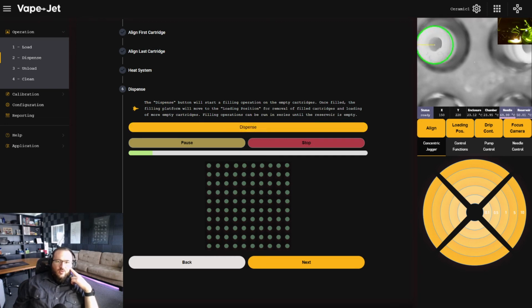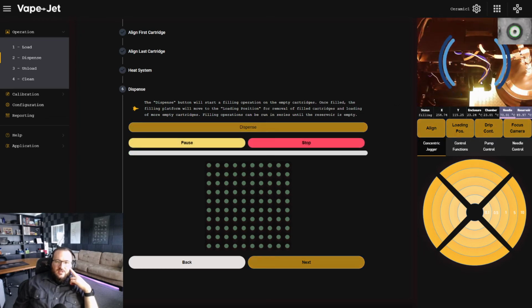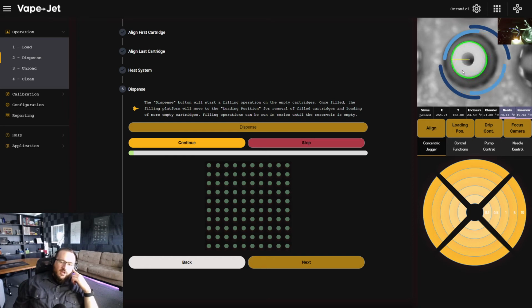Now, I'm going to hit dispense, and we're going to talk about what the machine is doing, and we're going to pause and stop it in a few places. So I'm going to hit dispense, and I'm going to switch camera views for a moment. See, it scans the tray, moves to position 1, and it's inserting the needle and performing the fill cycle now. Now, I'm going to hit pause, and we're going to walk through all the different functions the system is taking. So step 1, it moved to where the cartridge should be. Now, as you'll recall, these foam trays are not perfectly aligned. So what we have to do is we calculate where the cartridge should be, and then we measure where it actually is. So when I hit continue, you're going to see the system pull this cartridge directly into the center of its view.